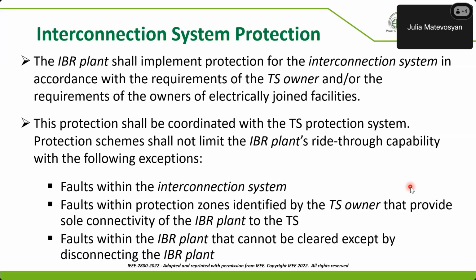This is no different than setting any other protection out there on the grid. There has to be proper coordination and layers of protection. The standard calls for that. Protection schemes, again, whatever is implemented, shall not limit the plant from riding through the requirements of the standard. Exceptions fall on the tie line itself. Well, there is no point in riding through a fault on the tie line, right? The plant is eventually going to trip no matter what. Protection within the plant, if the collector bus is faulted, well, there is no point in riding through. So there are some exceptions like that included in the standard. And I think that is my last slide.